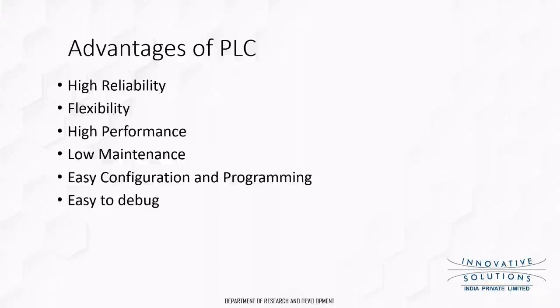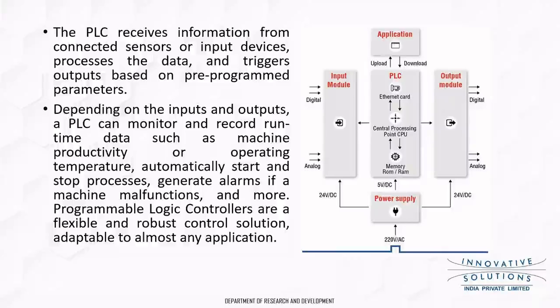This is the general architecture of PLC. There is an input module and an output module, but the CPU is always isolated from the input and output modules with the help of optocouplers, transistors, or MOSFETs, so that even if there's a fault at the input or output side, the controller should not get damaged.